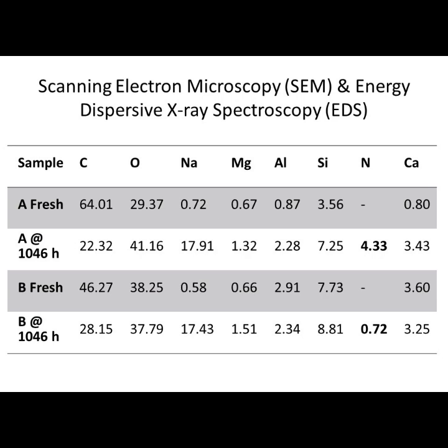However, this carbon decrement in the tracking resistant FRP rod was found to be less. In both samples, nitrogen was also detected, which is evidence of nitric acid formation under the impact of the electrical discharges. However, the nitrogen content was found to be more in sample A, which indicates that more severe electrical discharges took place in the normal FRP rod sample. The sodium content is increased drastically in both aged samples, which could be from the contamination solution, which was made from NaCl with tap water.